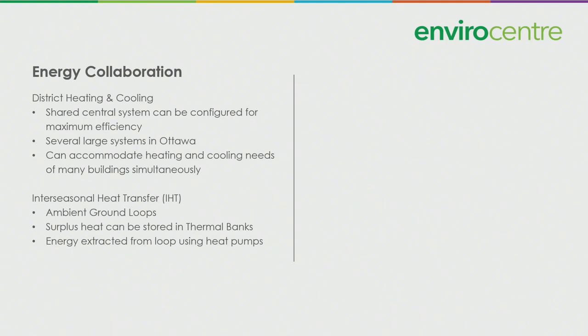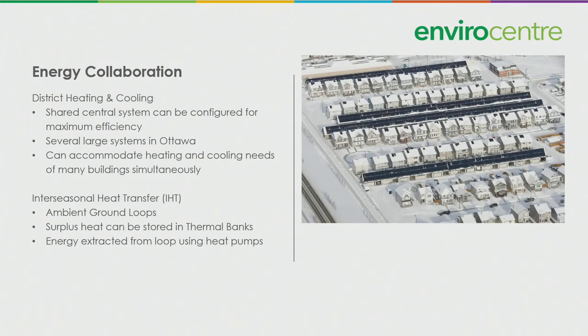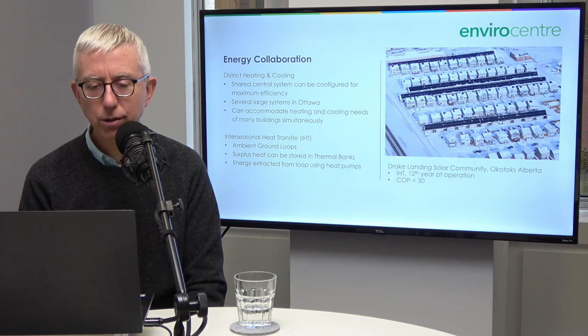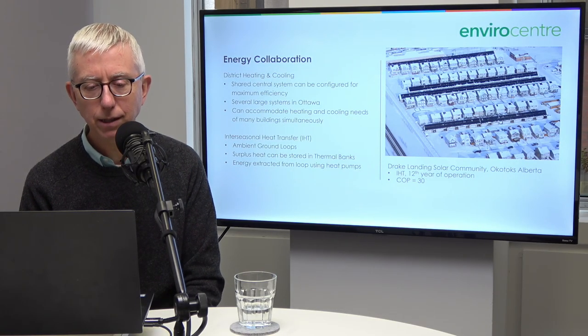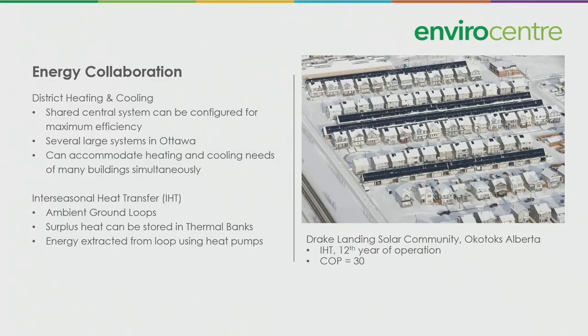You also have interseasonal heat transfer. This is something that has now been going for quite a while. And here's a picture of a system that was installed in Okotoks, Alberta. What they do is store the heat in the ground and then extract it. In the summer, you store the heat deep underground, and in the winter, you take that heat back out. So it's stored for very long periods of time, and they are incredibly efficient. I don't know if you can see the number there for the COP, but it says 30. So they are not 300% efficient. They are 3,000% efficient. You get a lot of energy out of them compared to the amount of energy you put into them. So they're incredibly efficient.